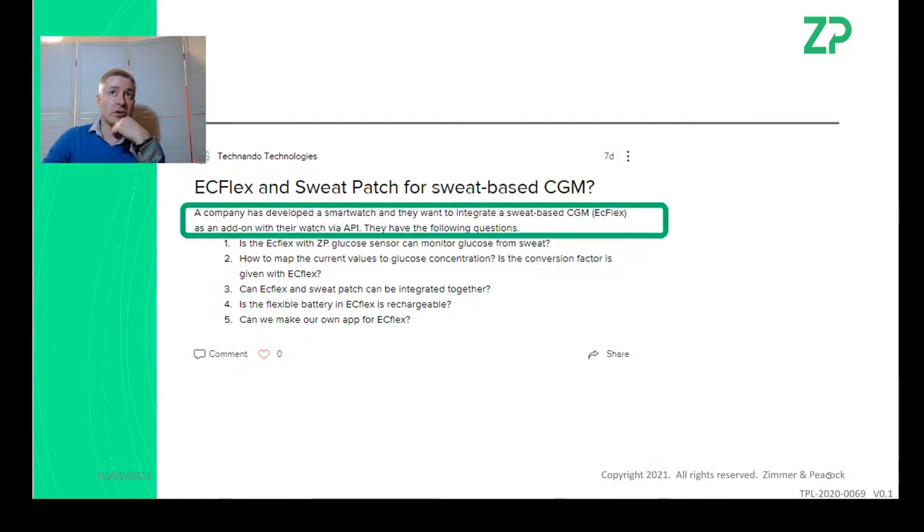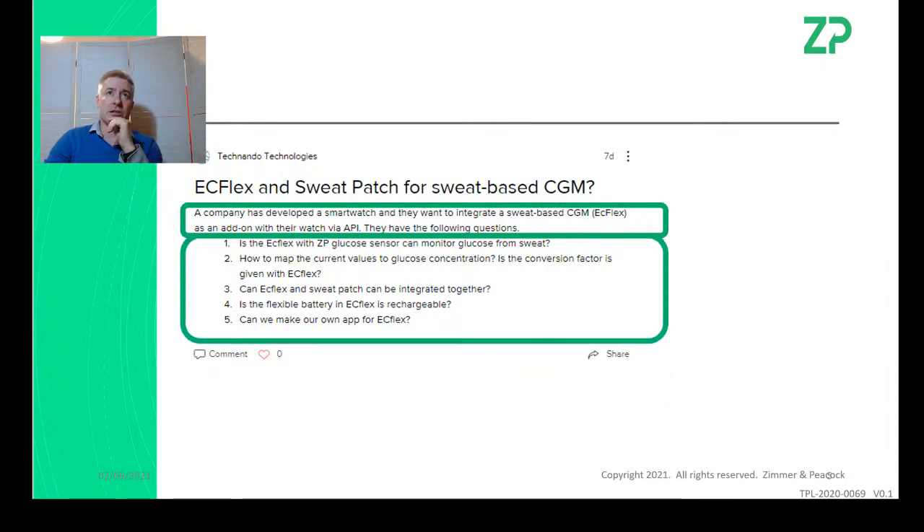The quick answer is: yes, we can measure glucose in sweat using the sweat patch, one of our glucose sensors, and the EcFlex. Then there were technical questions around calibration — the biggest one being: if I get a current reading, how do I know what the glucose concentration is? We have not calibrated our glucose sensors for sweat applications. Every time you change the matrix, the calibration factor changes.